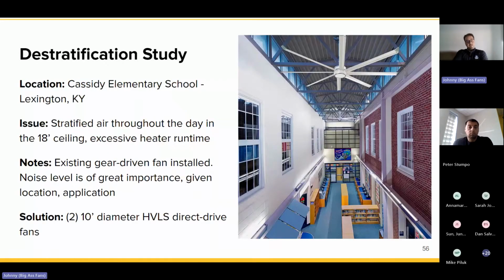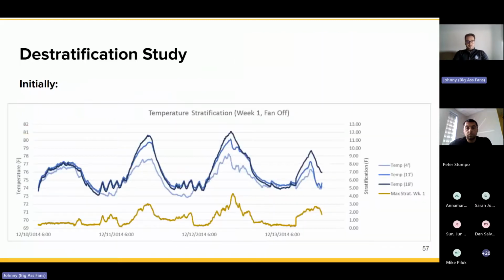On the commercial side, there are applications that call for this as well. This was another study we did, a similar type of study where we set temperature sensors throughout, looking at what the stratification effect is and how we can reduce it. This was a library, a tall common area. We use smaller fans, but ultimately achieve similar results. In this study, you can see the temperature delta in the blue lines, that's floor to ceiling, from 4 feet up to the highest sensor, which was 18 feet. The orange line shows you that stratification deviance over time.